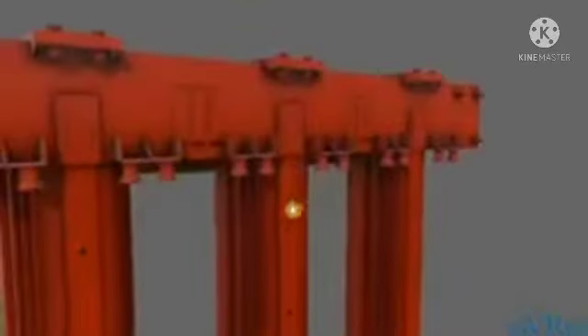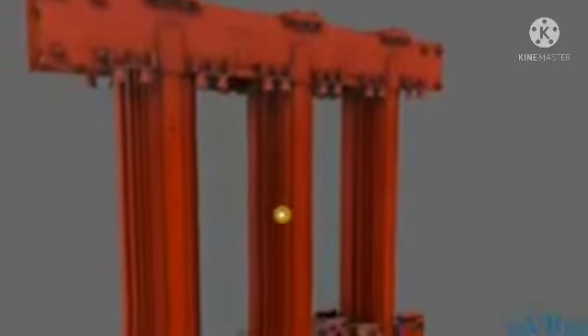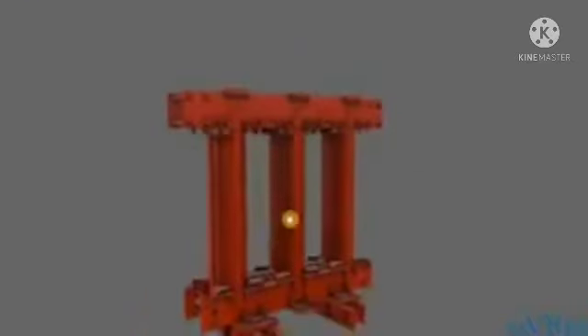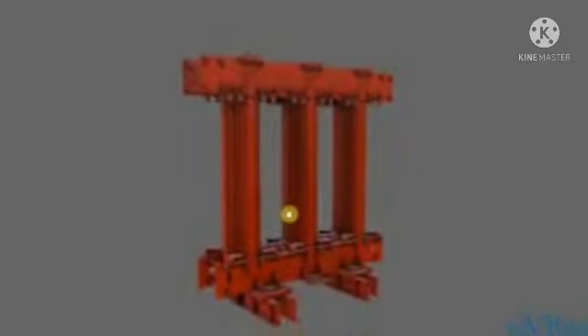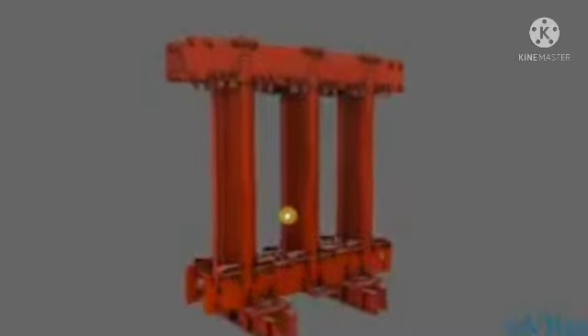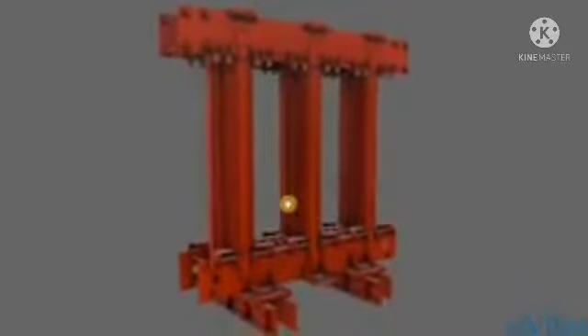This type of core could be used for a dry type transformer, a hermetic type transformer, or a conservator type transformer. The design does not change that much. The only noticeable change that you will see is if you are using a single phase transformer instead of a 3-phase transformer like that currently shown. So now we've had a look at the transformer core, let's go and have a look at the next item on the list, which is going to be the windings.